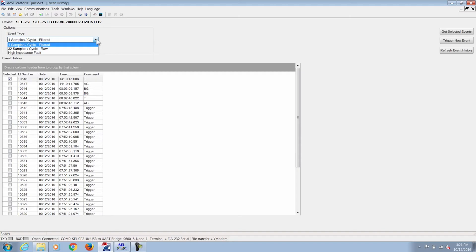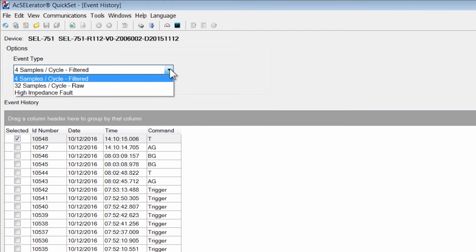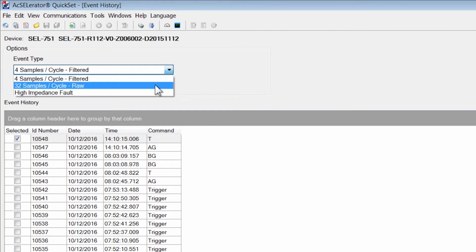If you're looking at CT saturation, transients, transformer inrush, or arc flash, you would want to retrieve the raw event from the relay, which is the 32 samples per cycle event.